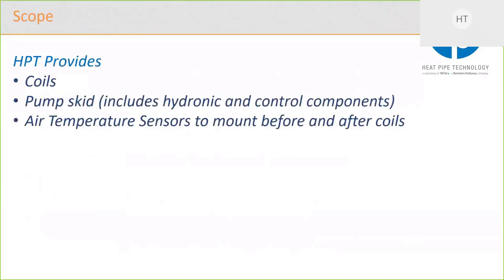So in terms of the scope, this is what HPT provides. We provide the coils, and as I said, because it's a whole system, we provide the pump skid. And on that skid, there's the hydronic components like expansion tanks, airflow separator, pumps, that sort of thing, and also the control components, the sensors and the control panel. We also provide air temperature sensors. Those are mounted before and after the coils, and they would ship loose because they can't be mounted on the pump skid.